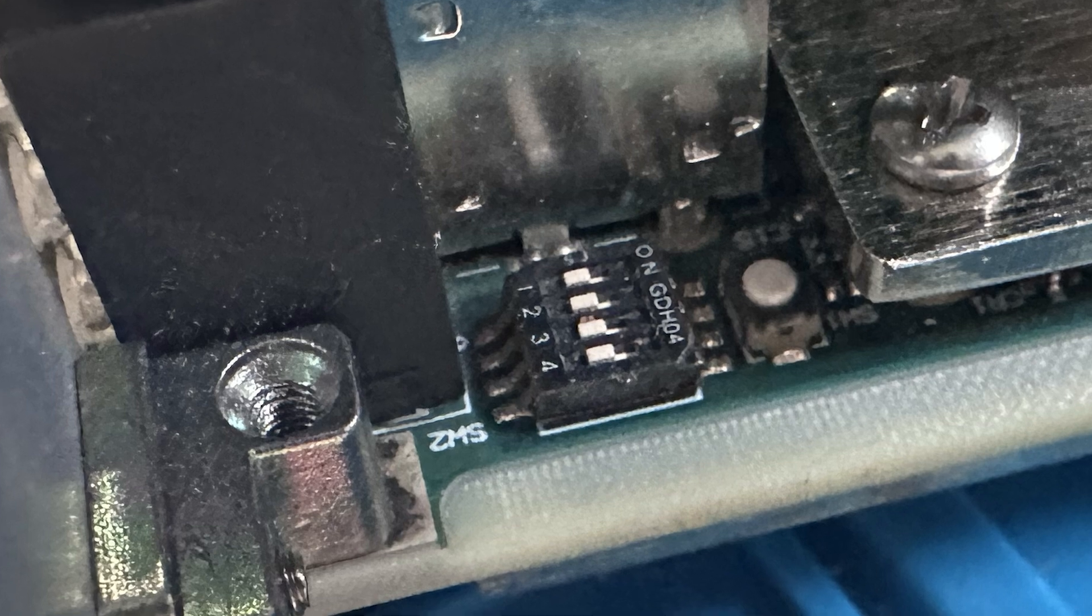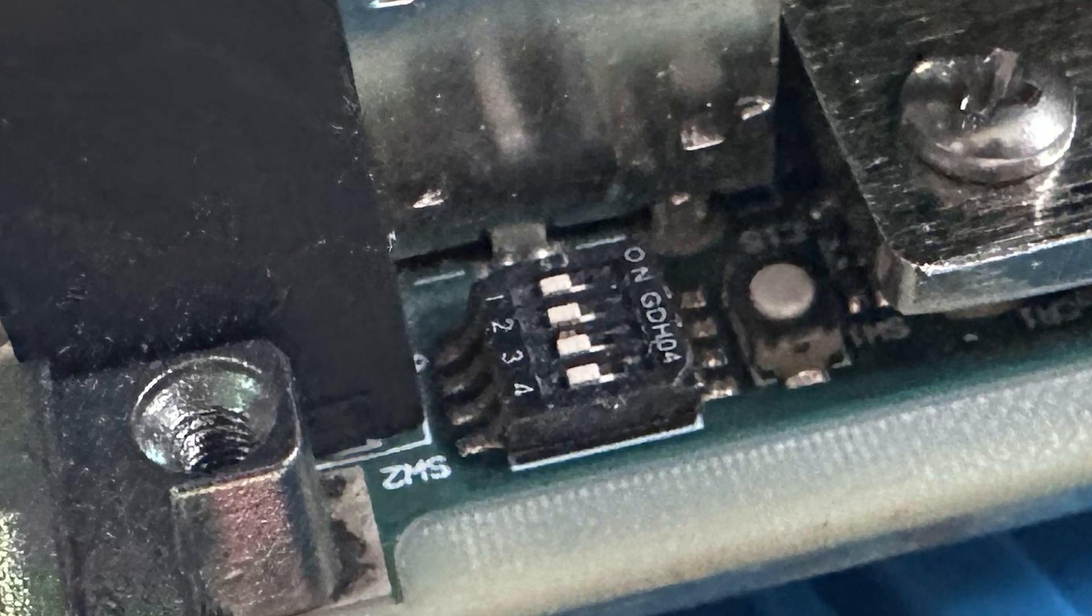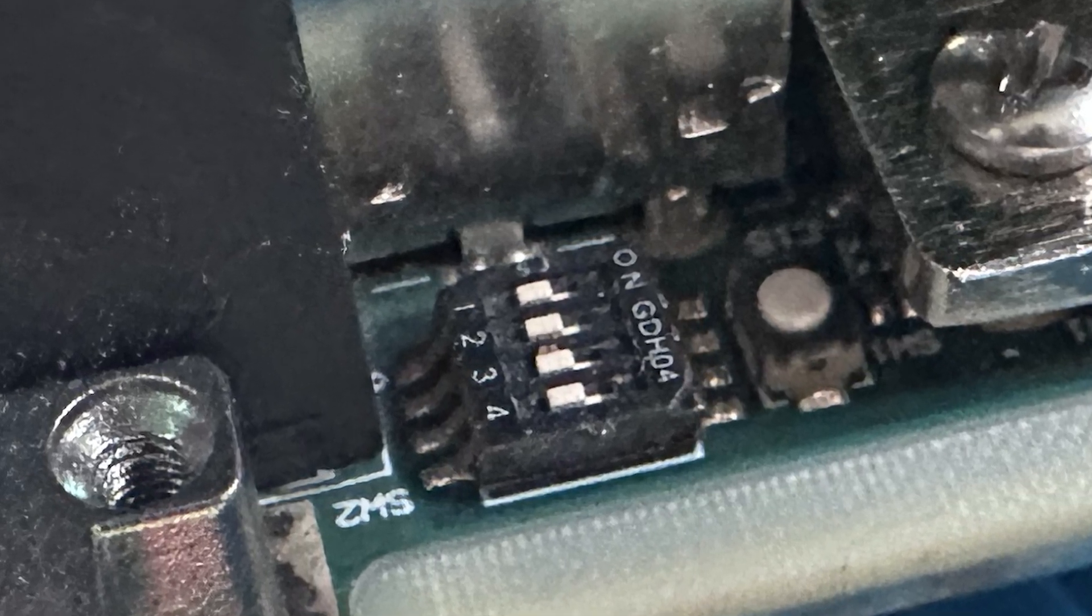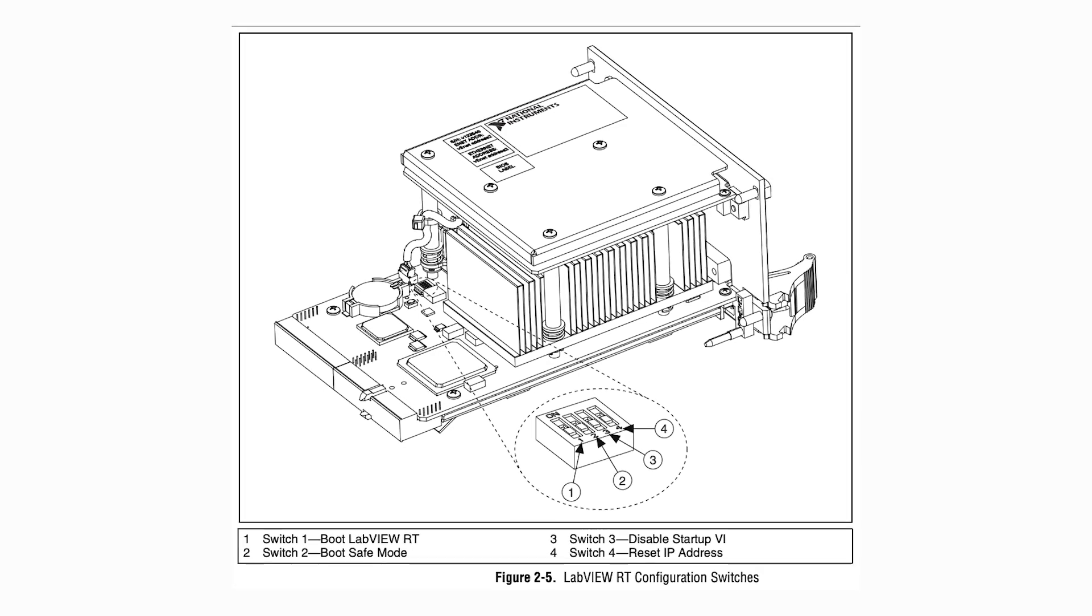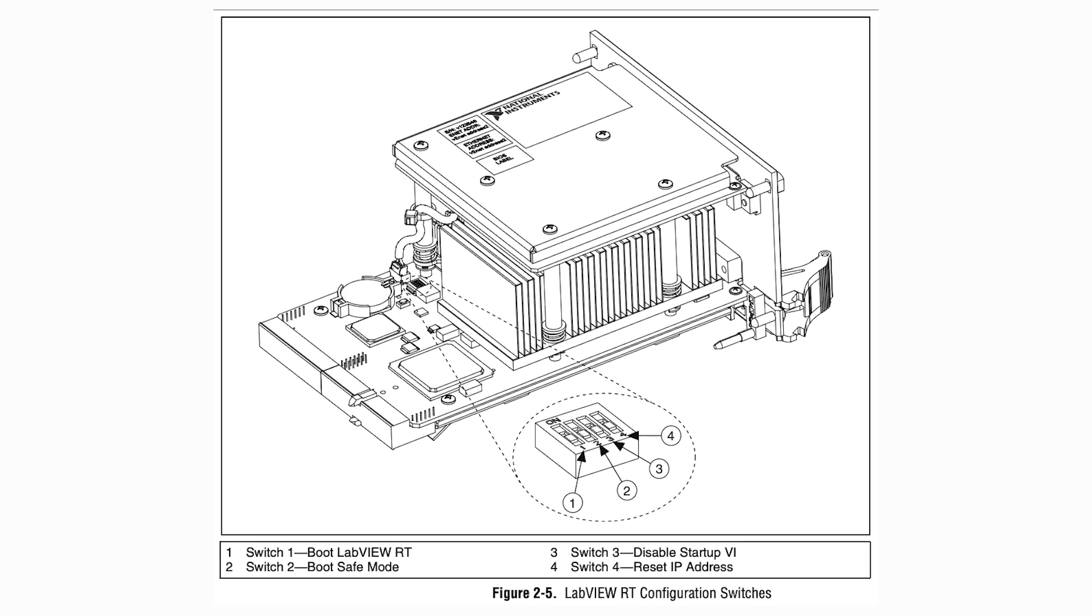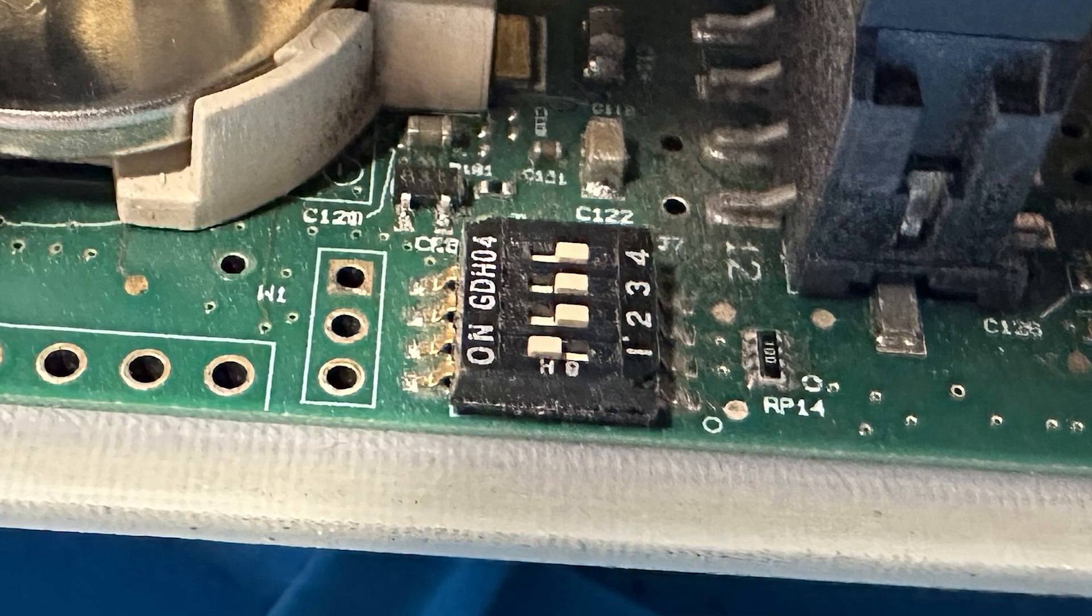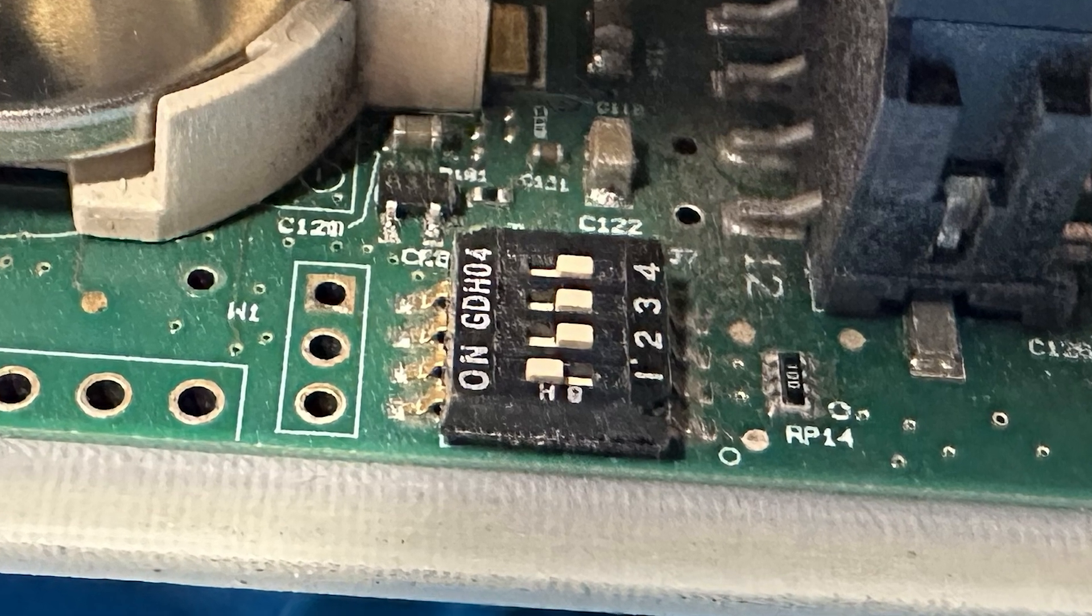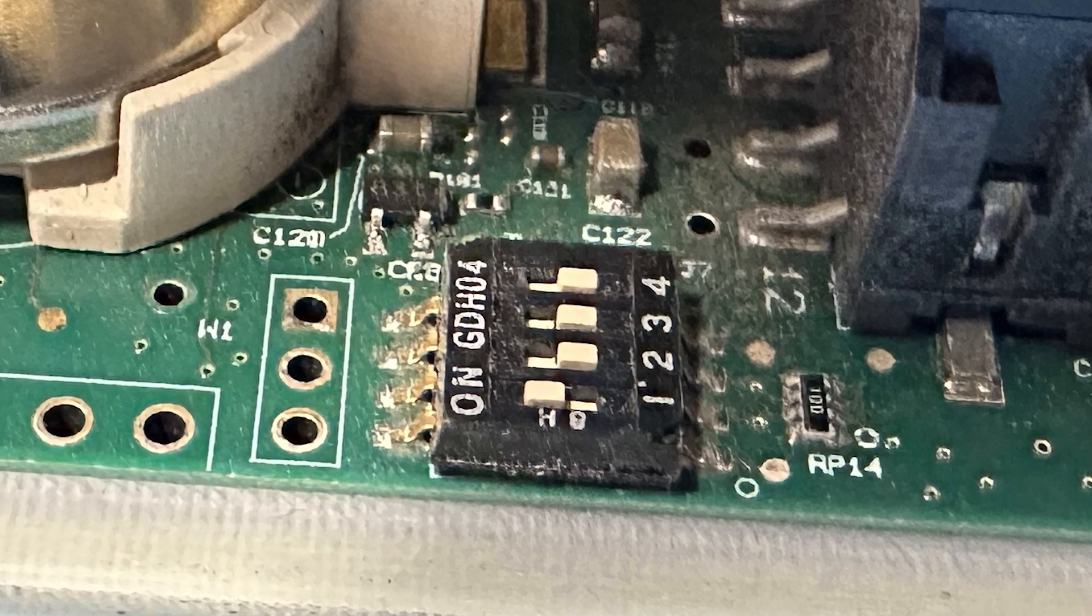Inside the PXI controller, you'll find a set of hardware configuration switches. Refer to your device's manual or this photo for reference. Using a flathead screwdriver, toggle switch 1 to the on position. This signals the system to boot into LabVIEW real-time mode.